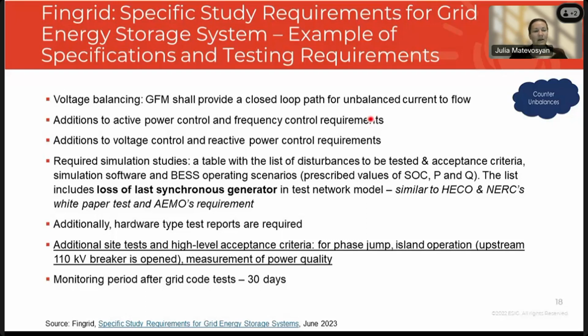And what's interesting, and I underlined here, I think that's the only example where I've seen so far, there are physical tests that are required. Maybe FNN has some physical tests as well. But this one too will have a physical test for phase jump and island operation, where they will disconnect the upstream 110 kV breaker and expect grid forming to support that part of the grid that got disconnected. And measurement of power quality, and they require a monitoring period of 30 days after the grid-forming battery becomes commercial.